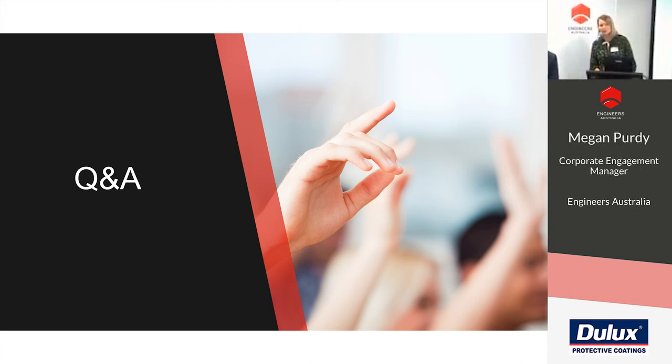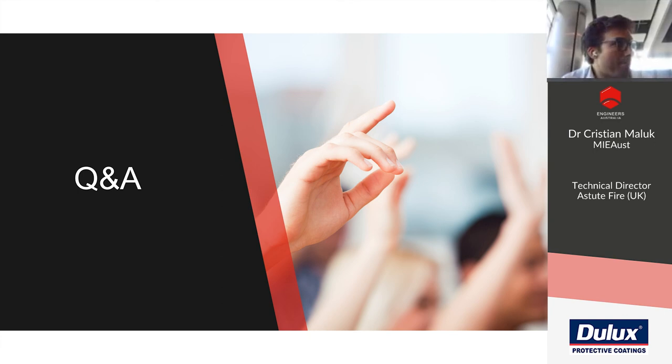Christian, did you want to add to that answer? Yeah, to be honest, I agree with what Suki just said. When you're dealing with concrete-filled steel tubes, you basically change the conditions of what the intumescent is experiencing, and the concrete in a certain way acts as a heat sink, which, as you might imagine, changes the thermal conditions of what's taking place.